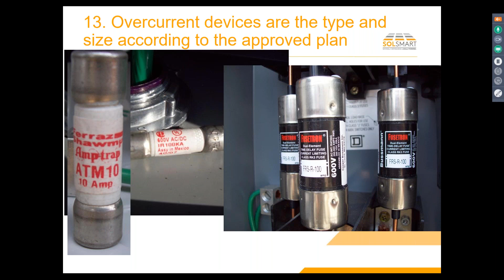Okay. Here's an example of a Class R fuse. It's got a 600 volt rating on it. A nice big number there. But if you look at the fine print, it's only rated for 300 volts DC. And so that was a common field mistake because these are readily available Class R fuses, and the 600 volt fuses were more expensive and special order.